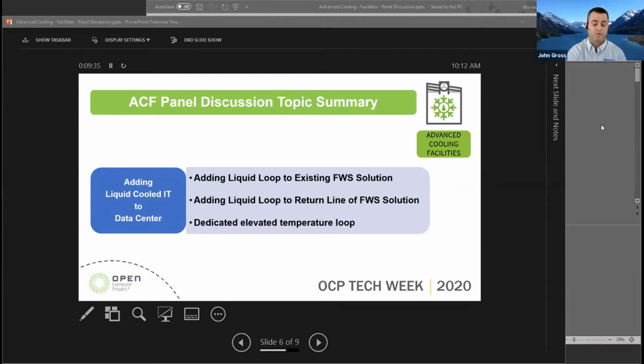your facility side pumps are separated from your ACS by a CDU. But the habit we get into when designing facilities is to look at steady state operation, which is our quote unquote design condition. The thing we have to keep in mind is that there's the design condition that we expect to see every day, but then there are events that we know are going to happen during the course of the facility's lifetime. And being critical facilities, which cannot go down when those types of unplanned events happen, we have to take those conditions into account when designing the facility.